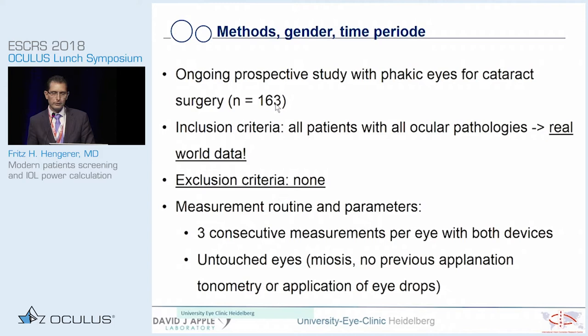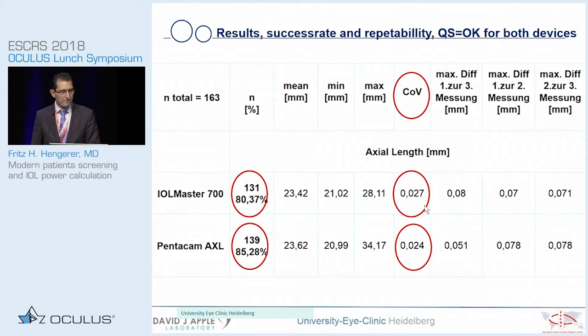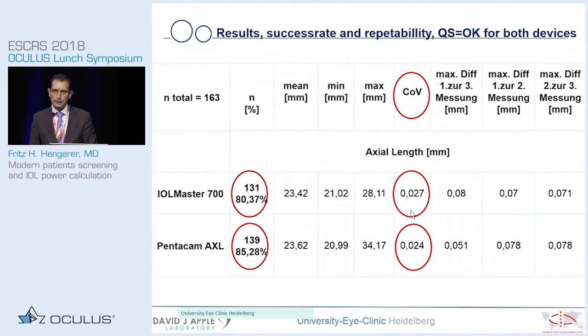We included all patients scheduled for cataract surgery with no ocular pathology exclusions. It seems a simple study but it isn't — we performed three consecutive measurements per eye with both devices. Eyes were left untouched, with no mydriasis, tonometry, or application of eye drops performed. Out of 163 eyes, the IOL Master 700 reliably measured 131 eyes, while the Pentacam measured slightly more. We then looked at coefficients of variance to address repeatability of consecutive measurements. Both devices proved very reliable, with the Pentacam showing slightly superior repeatability.